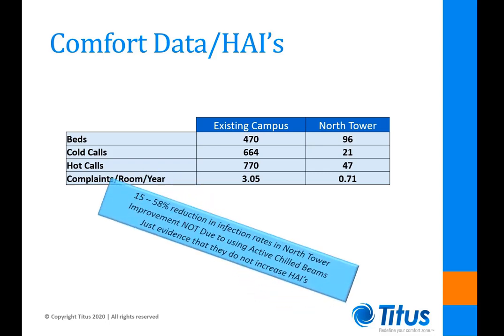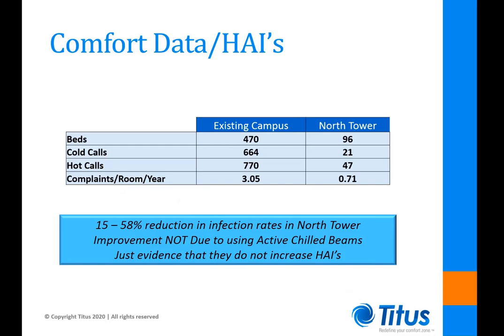One concern about recirculating units in patient rooms is that you are not exhausting the same volume of air as with an all-air system — bringing in two air changes and exhausting two instead of four — meaning the duration of exposure to an infectious aerosol is longer. However, the case study showed no increase in infection rates as a result of using the active beam system versus an all-air VAV system, confirming there was no increase due to the use of recirculating units in these spaces.